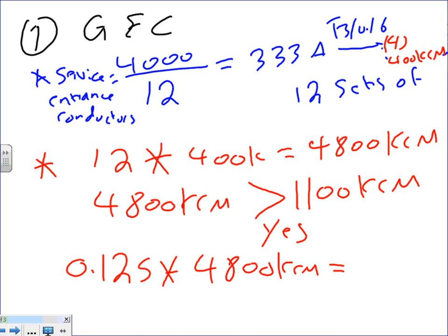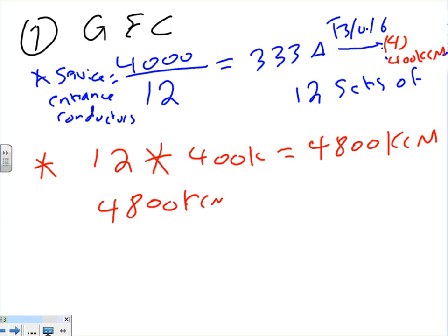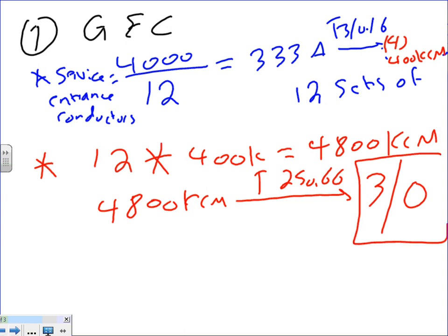I'm sorry, you don't have to do that one for the grounding electrode conductor. You don't have to do that one. This is for the bonding jumper. For the grounding electrode conductor, no need for this. So you take the 4800 kcm, take it to table 250.66, and that'll give you the largest, which is 3 aught. Done. The grounding electrode conductor is 3 aught. No question asked. That's the largest that you can do. Can you do a 250? Yes, if you want to, but the largest is 3 aught.